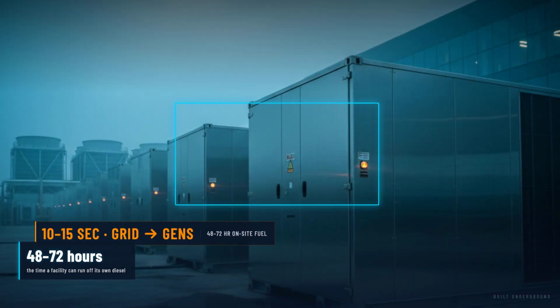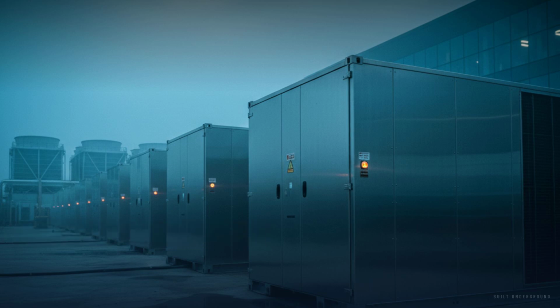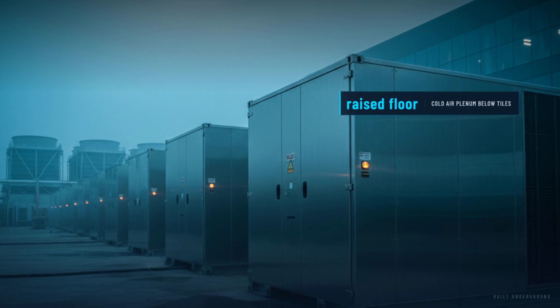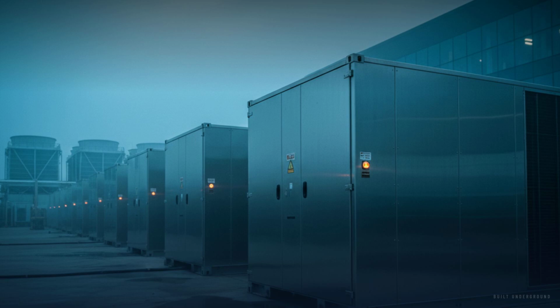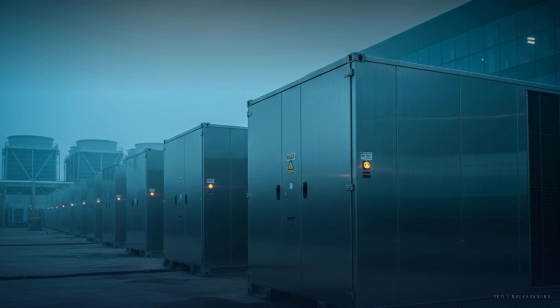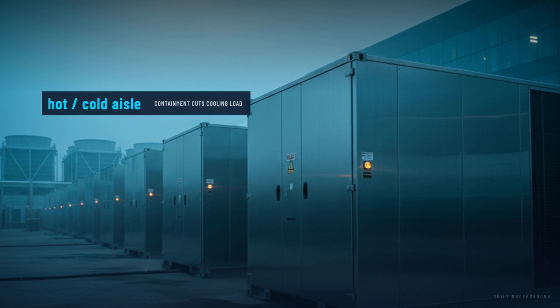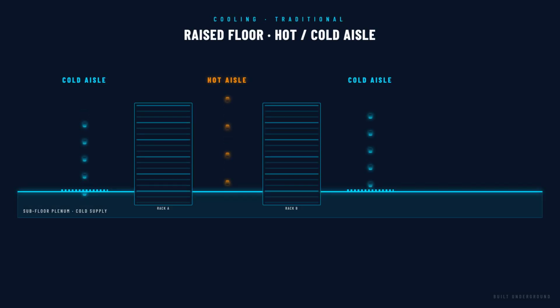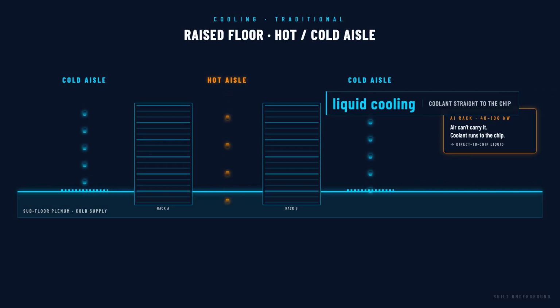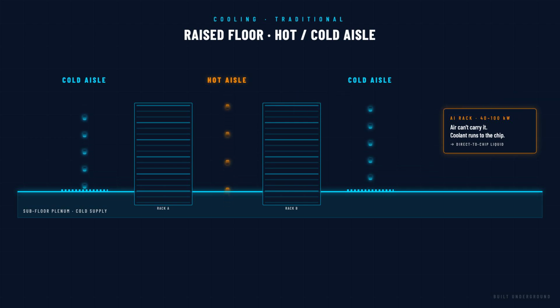On the mechanical side, cooling is the constant battle. Servers generate enormous amounts of heat. Traditional data centers use raised floor systems where cold air is pushed up through perforated tiles into cold aisles, flows through the servers, and hot air is extracted from the hot aisles and returned to cooling units. Newer facilities are moving to liquid cooling, where coolant runs directly to the chip level. This is being driven by AI training clusters that generate far more heat per rack than traditional compute.